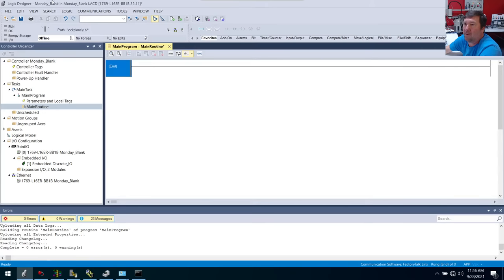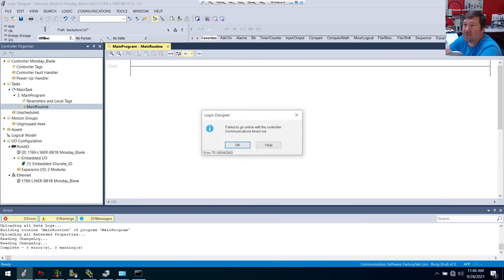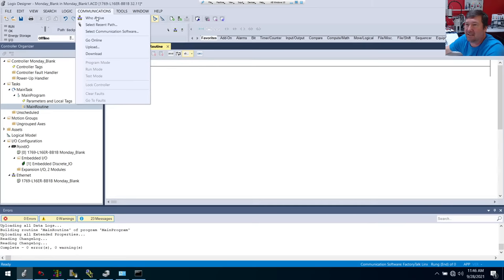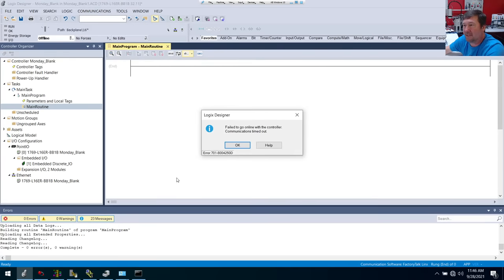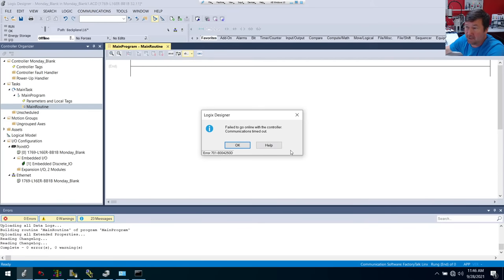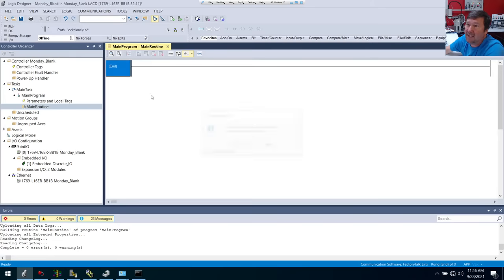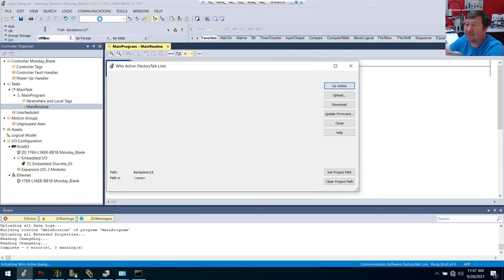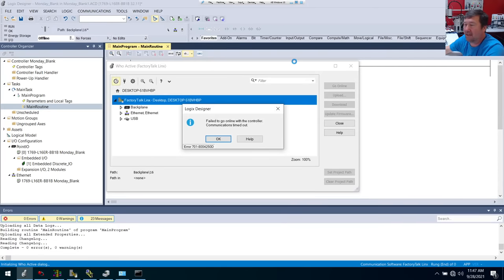We want to go online because we have our program right now. So I'm going to go to Communications and hit Go Online because I want to shortcut through this. And this is what happens if you don't get online every day: you get failed to go online for controller, communications timed out. And next, I guess I need to upload my program — we upload, communications timed out. And we hope we never have to hit the download button. And again, we're going to get communications timed out. That's why I like to use Communications Who Active, because it's going to take you through the steps you need to go through instead of just saying hey, I can't find this thing, go away.